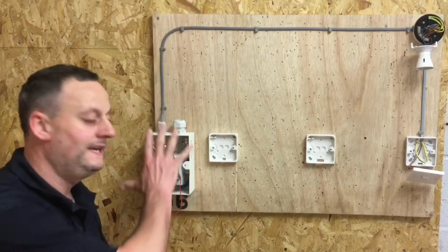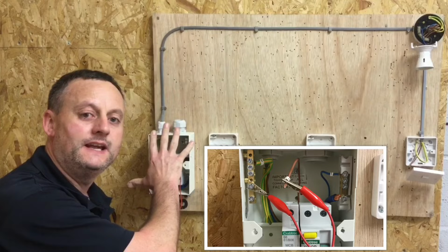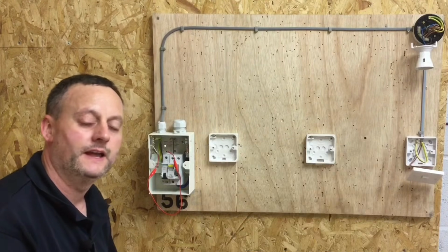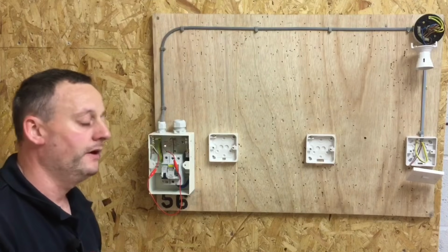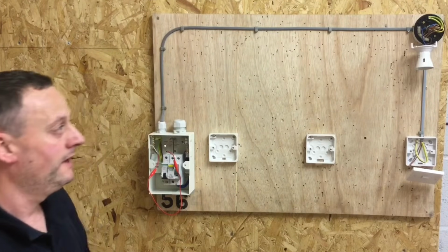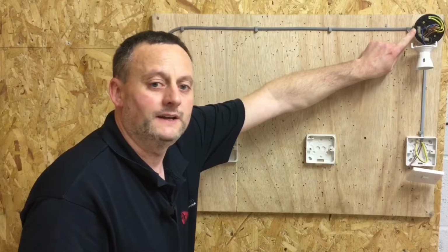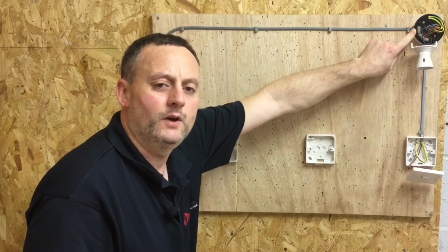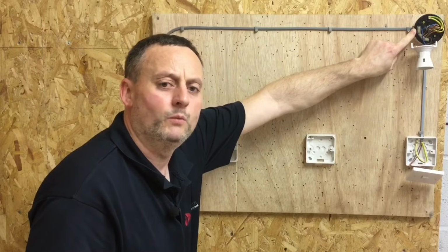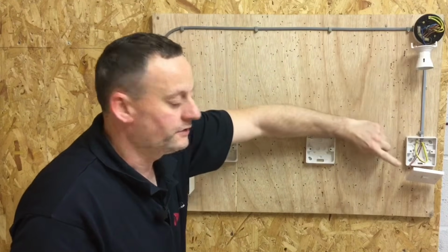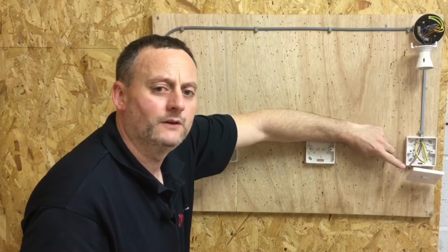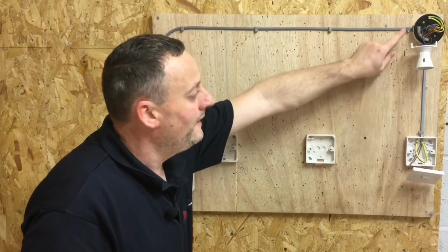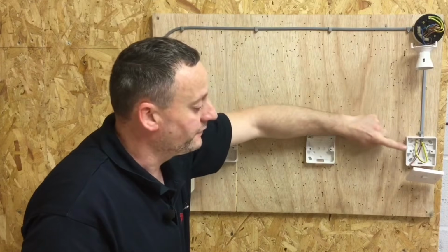So to recap then, we linked line and CPC in the distribution board itself. So the line conductor in the test, in this case the one for the lighting circuit, was linked to the earth bar. We only had one lighting point and one switch. We went to the furthest point, in this case of the radial circuit, and we tested between switching line and CPC, and we got a reading of approximately 0.13 of an ohm. We operated the switch at the same time we were there, and we saw full scale deflection of the instruments and went from the reading to infinity and back again. We left it in the on position before we go down to the switch.